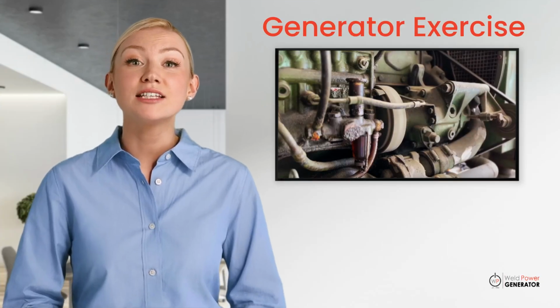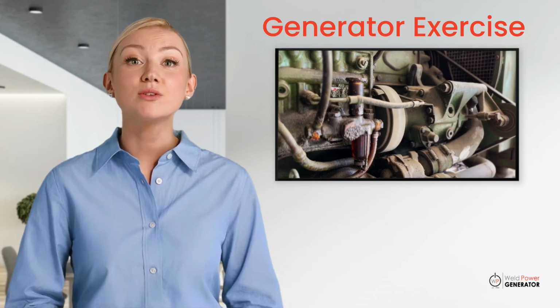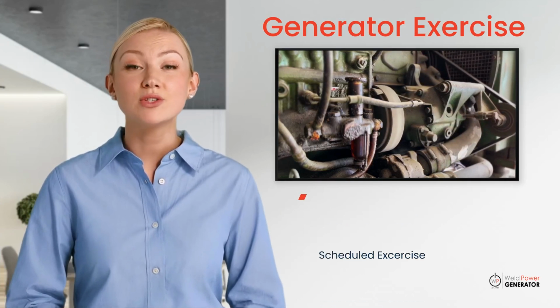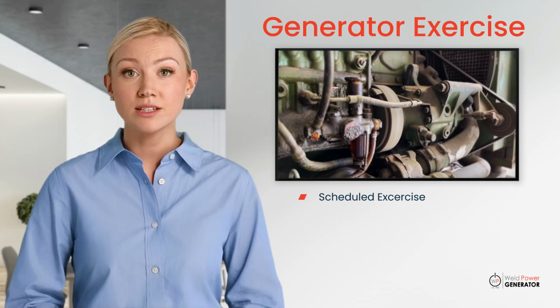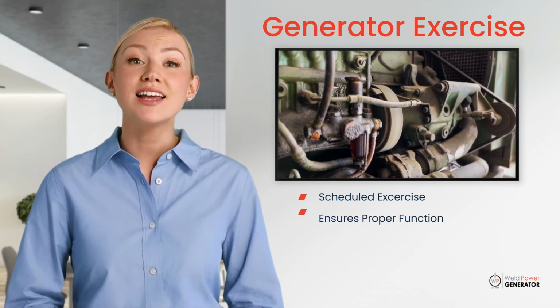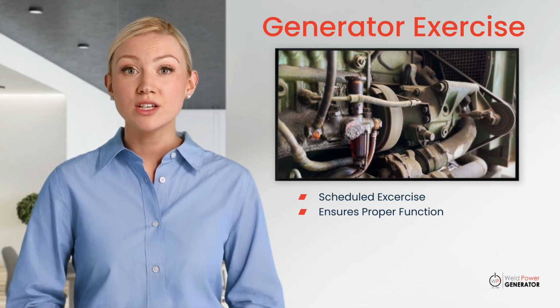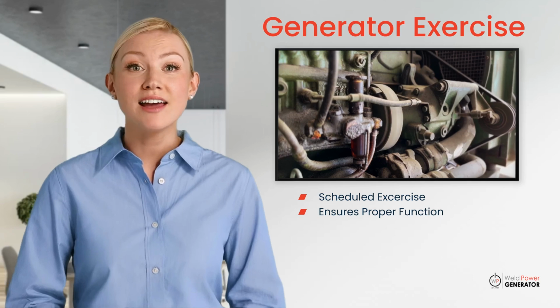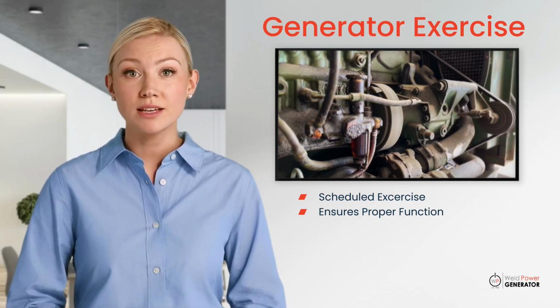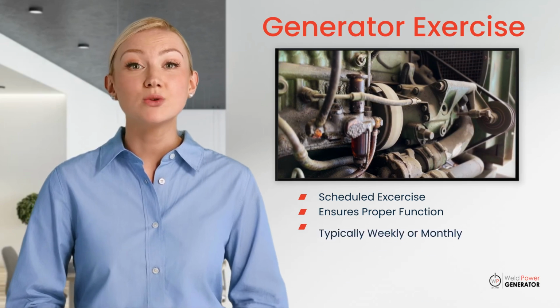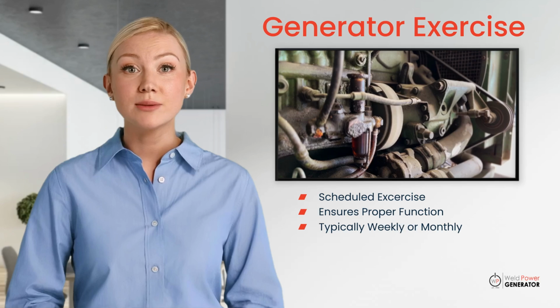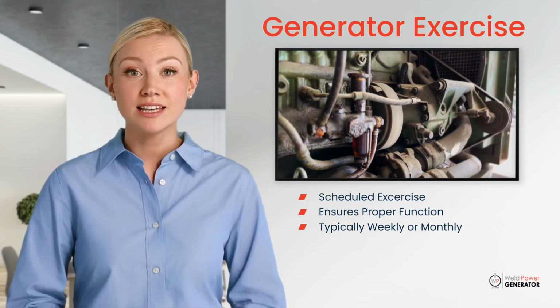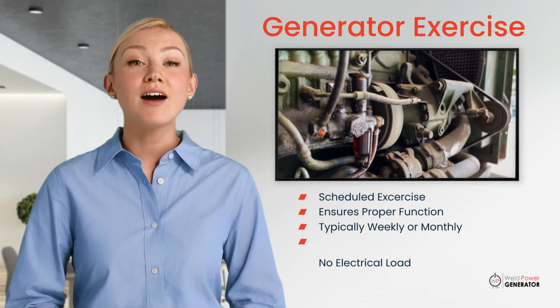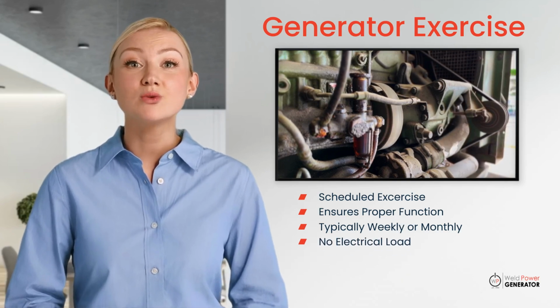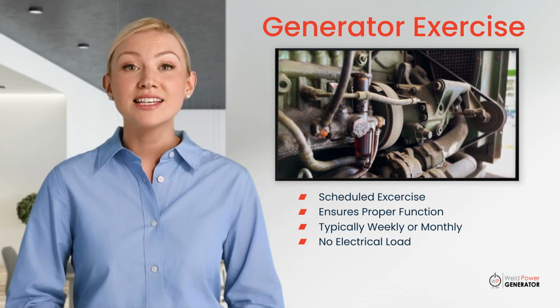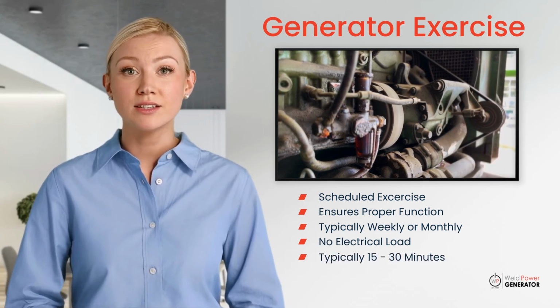Make sure that the generator isn't performing an exercise cycle. Most commercial and industrial generators are programmed to run automatically for exercise purposes. This periodic operation ensures that the engine remains in good working condition, circulates the fluids, charges the batteries, and verifies that all components function properly. Generator exercise is typically scheduled weekly, bi-weekly, or monthly, depending on manufacturer recommendations and facility needs. During this process, utility power remains active, and the generator runs without transferring electrical load. This typically lasts for 15 to 30 minutes.